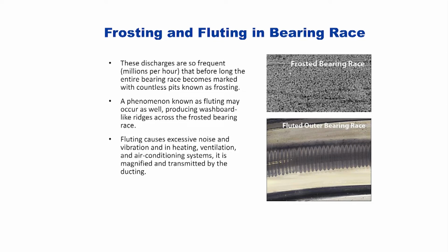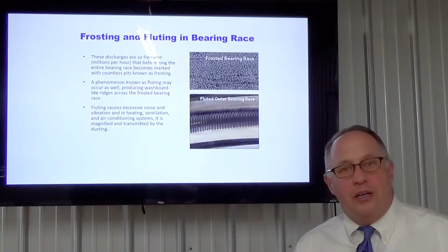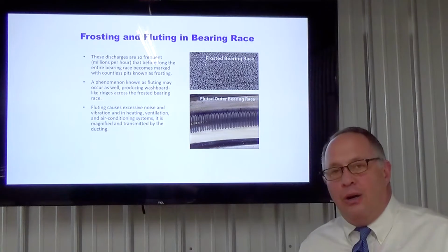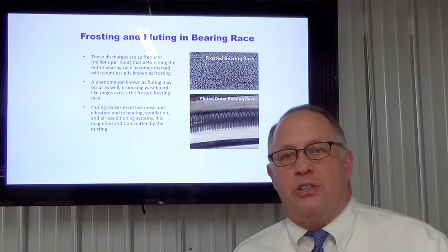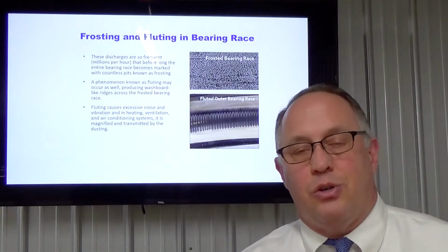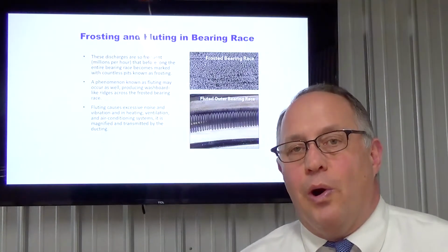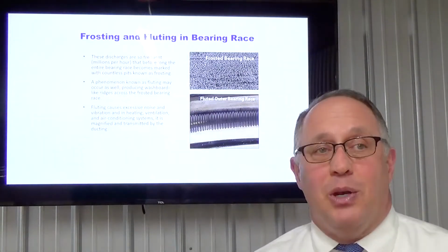outer bearing race itself. A phenomenon known as fluting may occur as well, producing washboard-like ridges across the frosted bearing race. Fluting causes excessive noise and vibration in heating, ventilation, and air conditioning systems. It is magnified and transmitted through the duct. So you can start to hear, and I've been in the presence of these hundreds of times, what happens is it starts to rumble or roar, kind of like there's something wrong.